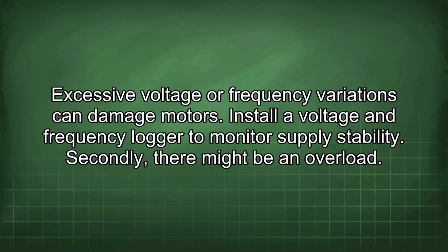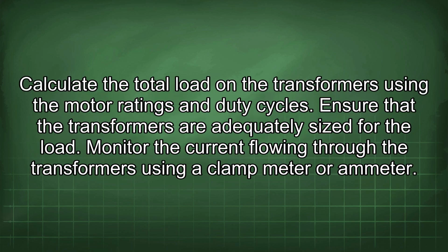Secondly, there might be an overload. Calculate the total load in the transformers using the motor ratings and duty cycles. Ensure that the transformers are adequately sized for the load. Monitor the current flowing through the transformers using a clamp meter or ammeter.